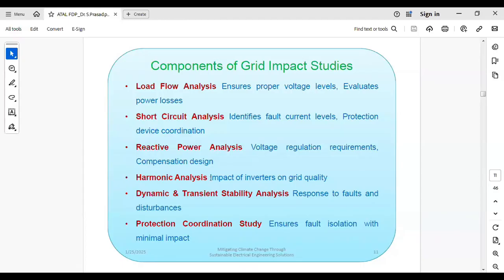Then harmonic analysis or power quality test. Basically, as you know, since we are using power electronics based inverters, there is a possibility of harmonics generation, voltage harmonics and current harmonics injection into the grid, and there are some acceptable limits according to CEA guidelines, which we need to follow. Based upon the harmonics generation, we have to decide what should be the size of the active or passive filter to be installed at the inverter station, so that the total harmonic distortion can be reduced, because with harmonic injection, more heating effect will be produced and more losses will happen in the system.